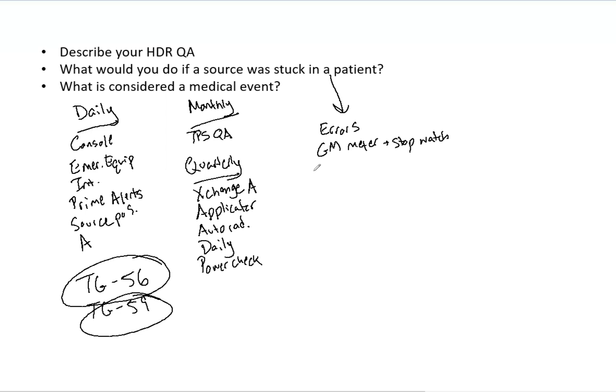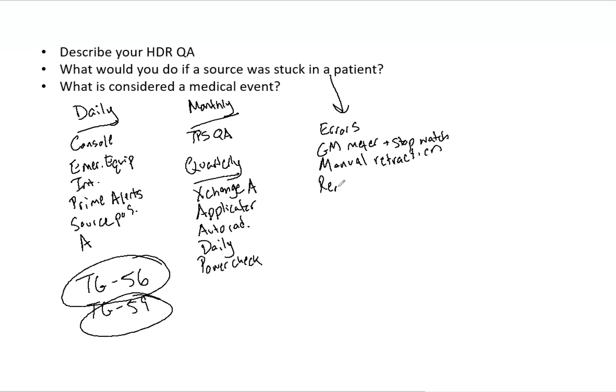So then at that point, you want to hit any type and every type of emergency interlock. See if those work. If that does not, then you want to do a manual retraction of the source. Then you want to use the Geiger meter to ensure that the source is retracted. And then if that isn't gone, if you still have activity and exposure, then you want to remove the applicator.